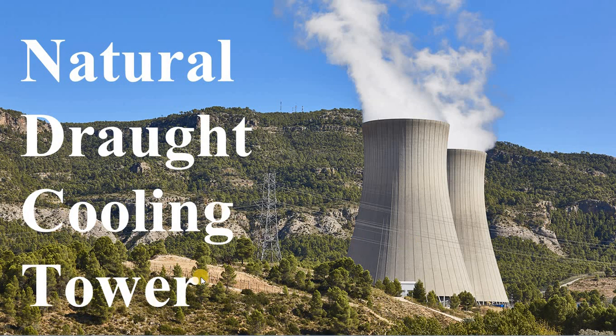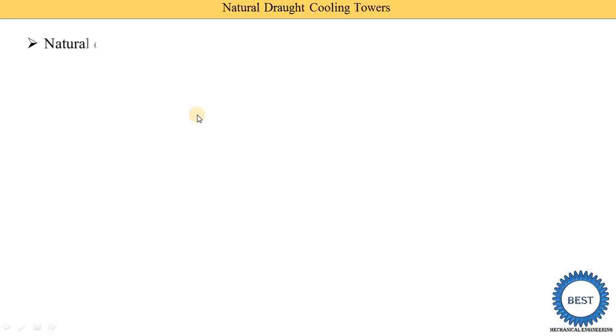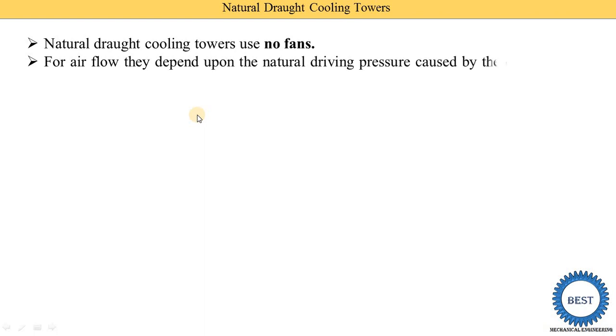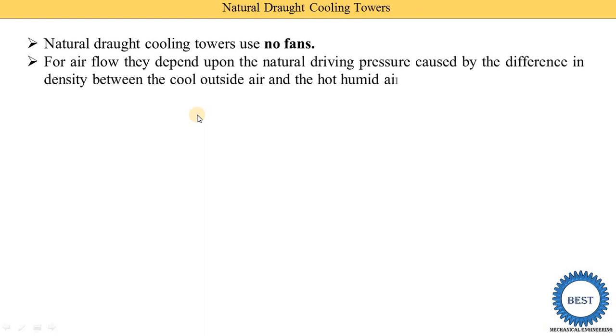The second word, cooling tower, means cooling of water is carried out in this tower. Cooling of water is carried out by using air, and air circulation is carried out by density difference — naturally, no fan is used. Circulation of air depends upon the natural driving pressure of air caused by the difference in density between the cool outside air and hot humid air inside.